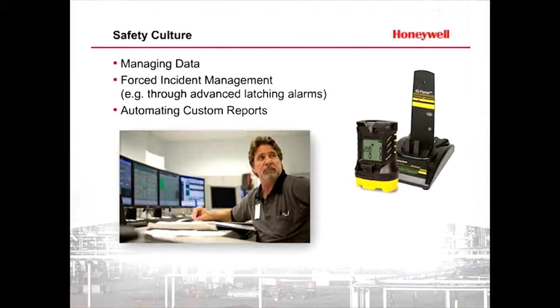So how can the IQ Force help? Take, for example, the advanced alarm latching feature in the instrument. When enabled through the IQ management software, when the detector goes into alarm, it'll stay in alarm until the instrument is docked. The dock will then send an email to a designated individual alerting them that someone has experienced an event. This ensures that every gassing event is recorded and dealt with immediately.